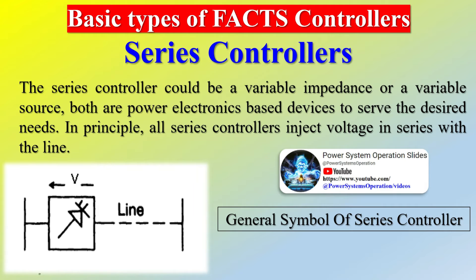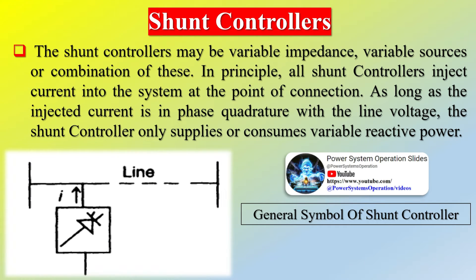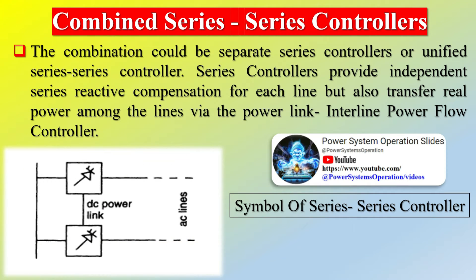FACTS is static equipment used for the AC transmission of electrical energy, meant to enhance controllability and increase the power transfer capability of the network. It is generally a power electronics-based device. FACTS is defined by IEEE as a power electronic-based system and other static equipment that provide control of one or more AC transmission system parameters. FACTS could be connected in series with the power system (series compensation), in shunt with the power system (shunt compensation), or both in series and in shunt.